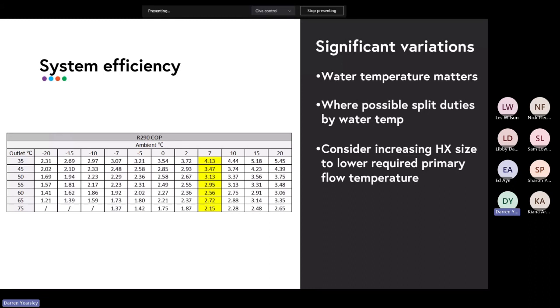If you combine that into one system and you run high temperature all the time and then you mix that water down for the low temperature application, the efficiency you'll get out of the system is about a half of what it could be. So you should always be asking your questions when you're doing these specifications. What's the lowest primary water temperature I can use to achieve the duty which I need to achieve?